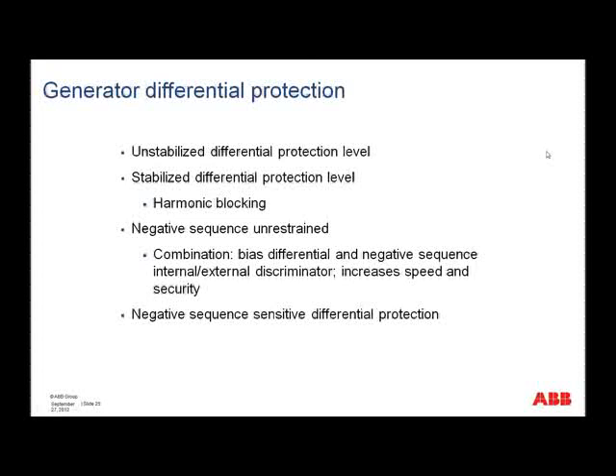Now, looking at the 87G function itself, what is it made up of? Well, first of all, we have the unstabilized differential protection level. This is the high set level. If the differential current goes above this level, then there's no doubt that the fault is internal. We have the stabilized differential protection level. Okay, this is your normal characteristic. And if we go into this operate area, it's not a direct permission to trip, but first of all we have to check with the blocking conditions to see whether a trip is permitted or whether we are in this operate area for some reason that is not actually a fault.